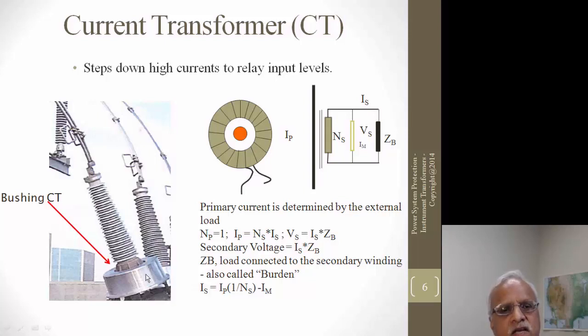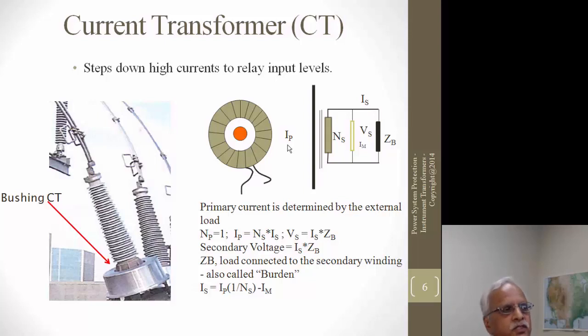In this example, the lead going into the breaker is just one turn, with the current transformer core mounted outside — this is how it is mounted on a breaker. The secondary current is the primary current divided by the turns ratio, produced by the ampere turns that push the current through whatever burden is connected. The voltage developed across the secondary is the burden times the secondary current, which is the primary current divided by the number of secondary turns.